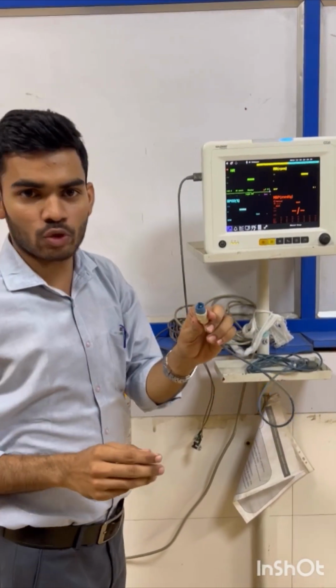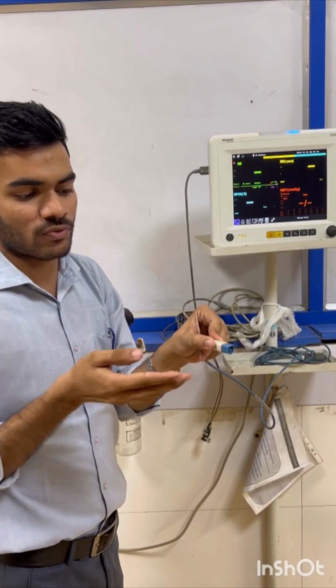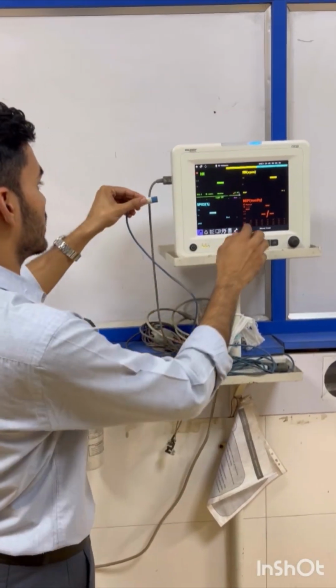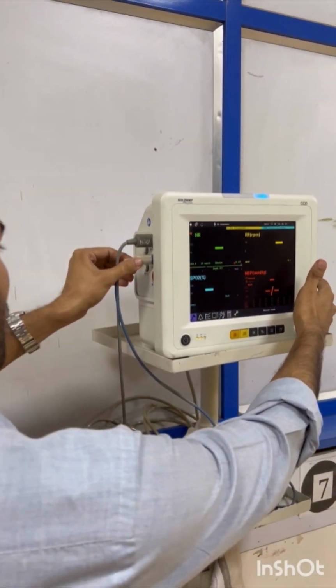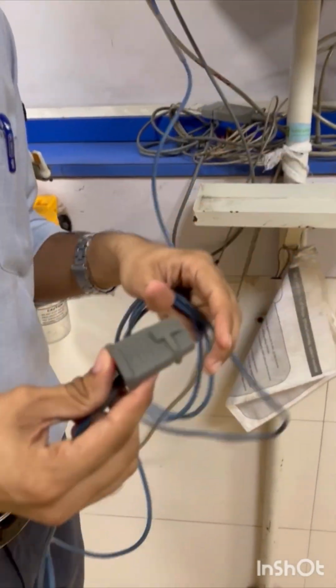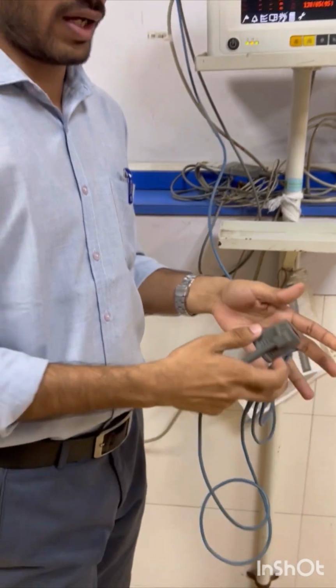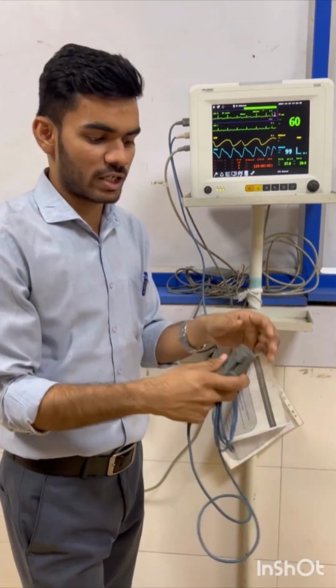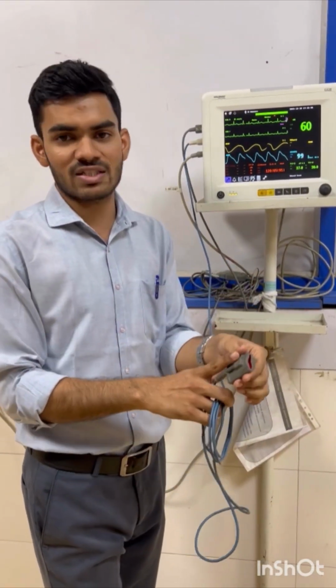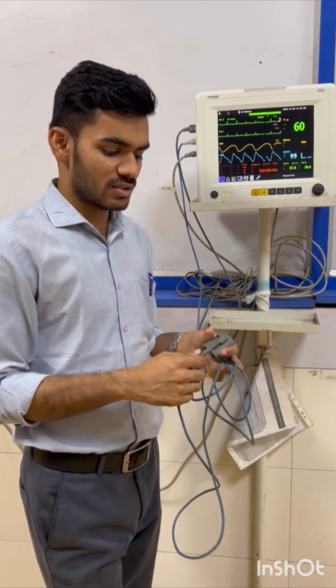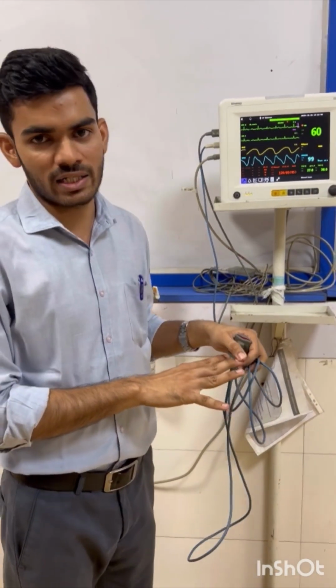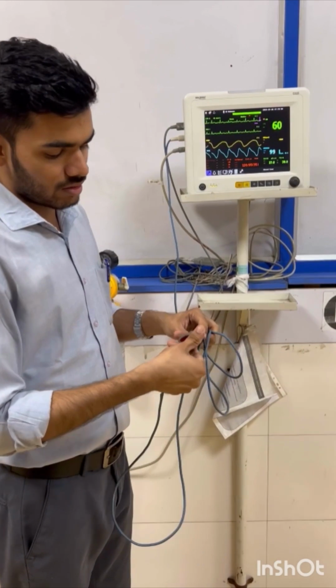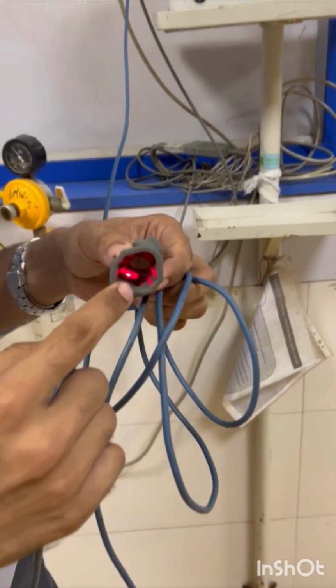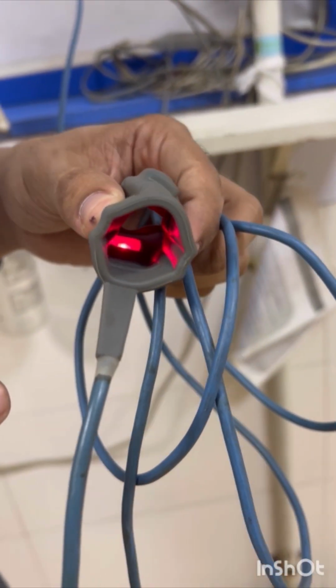Second one is SpO2 probe. The flat surface should face upward side, and then you have to connect it. SpO2 is blue color coded to avoid any disturbance. So if I have connected an NIBP cuff in this hand, I can't use this probe in the same hand. Second thing is, make sure the nails are properly cleaned, patient nails. There has to be red light inside the sensor, then only it can detect the SpO2.